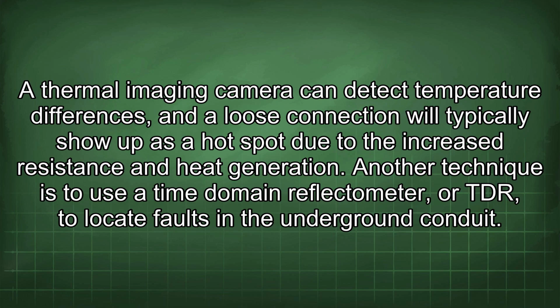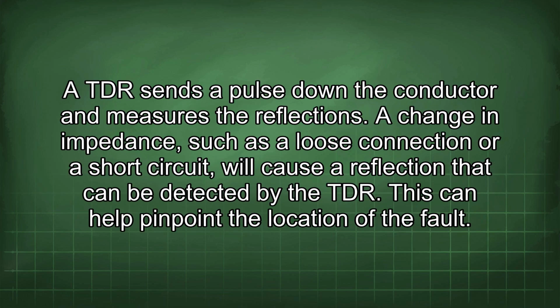Another technique is to use a time domain reflectometer, or TDR, to locate faults in the underground conduit. A TDR sends a pulse down the conductor and measures the reflections. A change in impedance, such as a loose connection or a short circuit, will cause a reflection that can be detected by the TDR. This can help pinpoint the location of the fault.